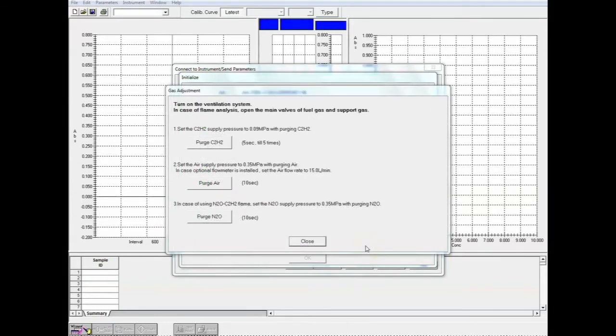So now we're getting a pop-up for gas adjustment. So it wants to check the gases to make sure that the fuel supply is okay. So it's asking us to turn on the ventilation system. So that's the fume hood above the atomic absorption unit. So that's already on. So now it wants to purge the acetylene. So we just hit that. And if you were here in the lab, you could hear a hissing sound that the gas is being purged. It actually wants us to do that 5 times. Okay, do it again.